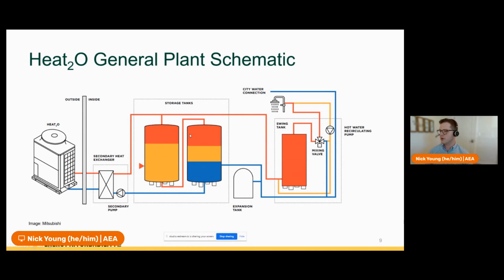It's sensing tank temperatures - it doesn't show those sensors on here, but there are generally at least 3 sensors inside the tanks. It's looking at that tank temperature, and then it's turning on. This secondary pump is looking at the primary side, and when it sees flow, it then turns on the secondary side to move water through that heat exchanger, charging the tanks from top to bottom, just like any single pass.